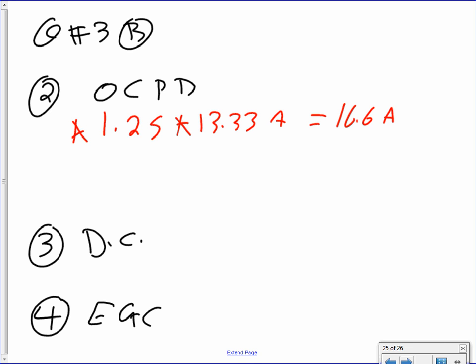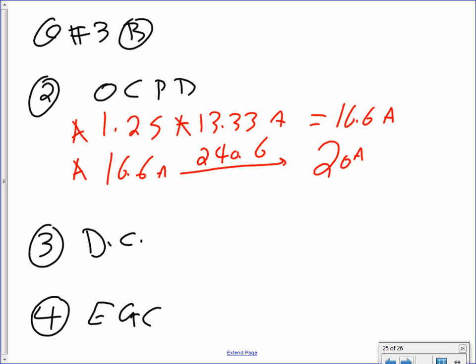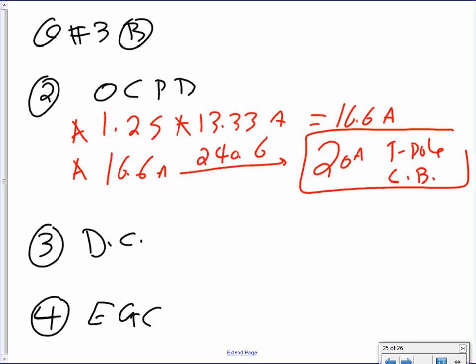And then you take this one, 16.6 amps, take it to 240.6. That'll get you a healthy what? 20 amp single pole circuit breaker. 20 amp single pole circuit breaker. Done.